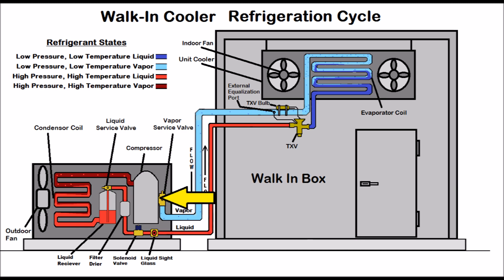You have low pressure low temperature vapor heading into the compressor. The compressor is located in the outdoor unit, which is the condensing unit. Low pressure low temperature vapor goes through the vapor service valve into the compressor — you should have vapor only heading into that compressor. Then you have high pressure high temperature discharge vapor gas coming out of the compressor. The compressor takes low pressure, compresses it into high pressure, and since it's high pressure it's therefore high temperature. Temperature follows pressure, and where it comes out of the compressor that's called the discharge line.